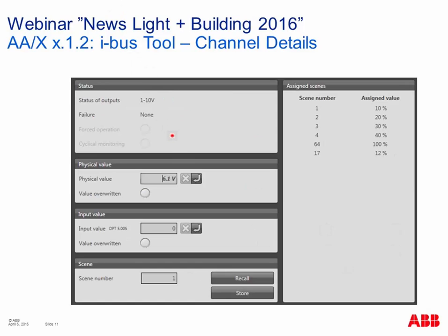The i-bus Tool screenshot shows the 4-fold component with channels A to D. Two channels are currently active — one with a 1 to 10 volt voltage output, the other with 0 to 20 milliampere. The momentary output value is shown, along with failure status and forced operation indicator. Cyclical monitoring of incoming telegrams can also be parameterized. Going deeper into each channel, you can see the real output signal — for example, 6.1 volt — and the incoming telegram value. You can override values for testing purposes and reset back to the original.